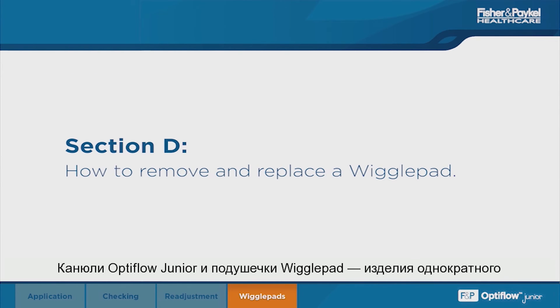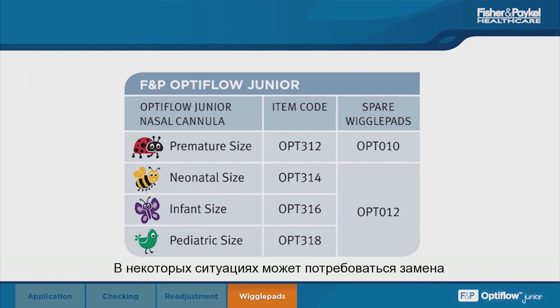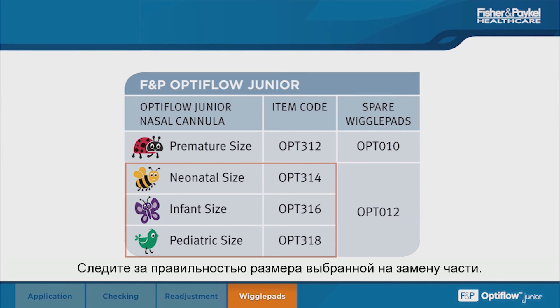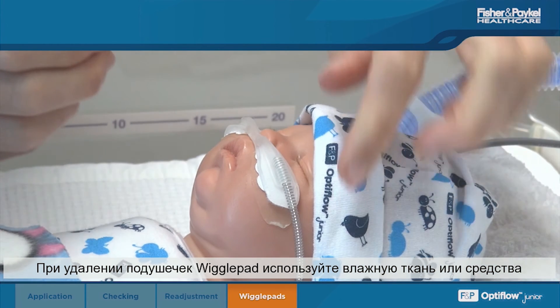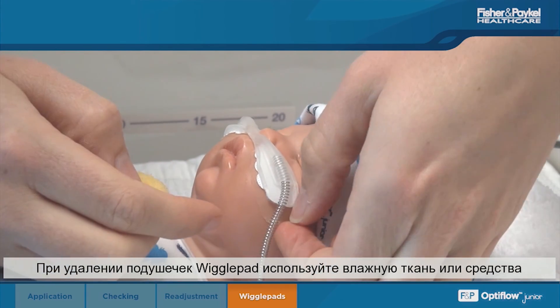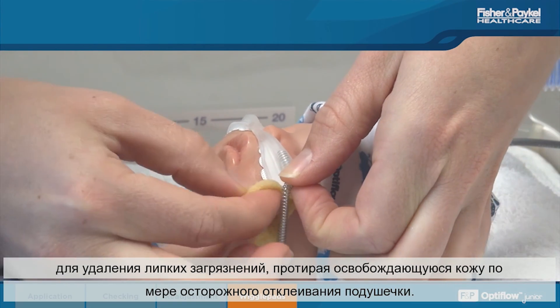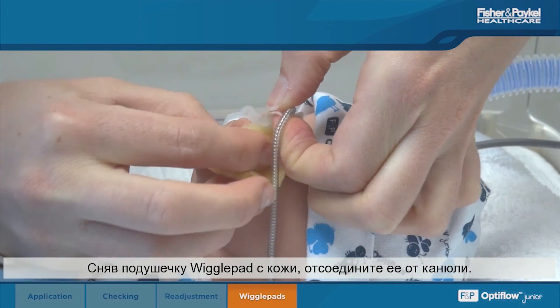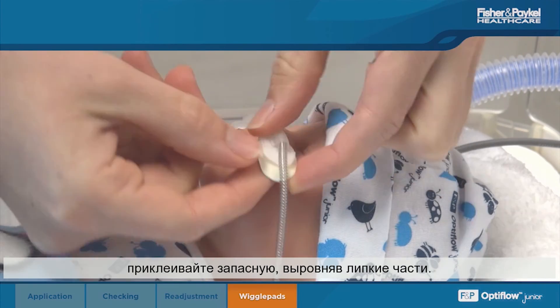The Optiflow Junior cannula and wiggle pad have a recommended single usage of seven days. In some cases, a single wiggle pad may need to be replaced independently of the cannula. Ensure that the correct spare size is chosen. When removing a wiggle pad, use a wet cloth or adhesive remover and wipe along its adhesive underside while gently peeling away. Once removed, detach the wiggle pad from the cannula.